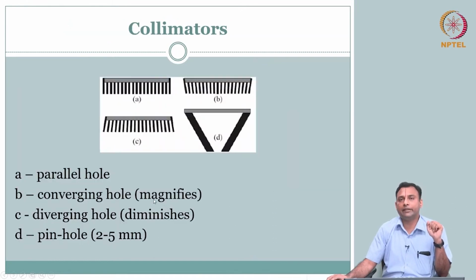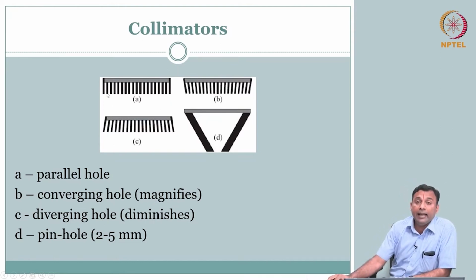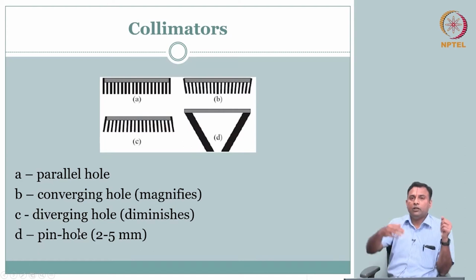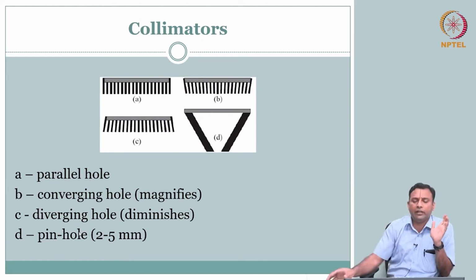First is your collimators. Collimators, very similar, in fact you know this. What is this? Oh, these are lead strips. Okay. So, you have different configurations. What is your objective here? The gamma photons are coming, you want only the gamma photons that are coming through the body in a straight line, that is the signal of interest. So, you want to allow for only that line of sight, very similar to what we did for X-ray. So, the different configurations that are possible.